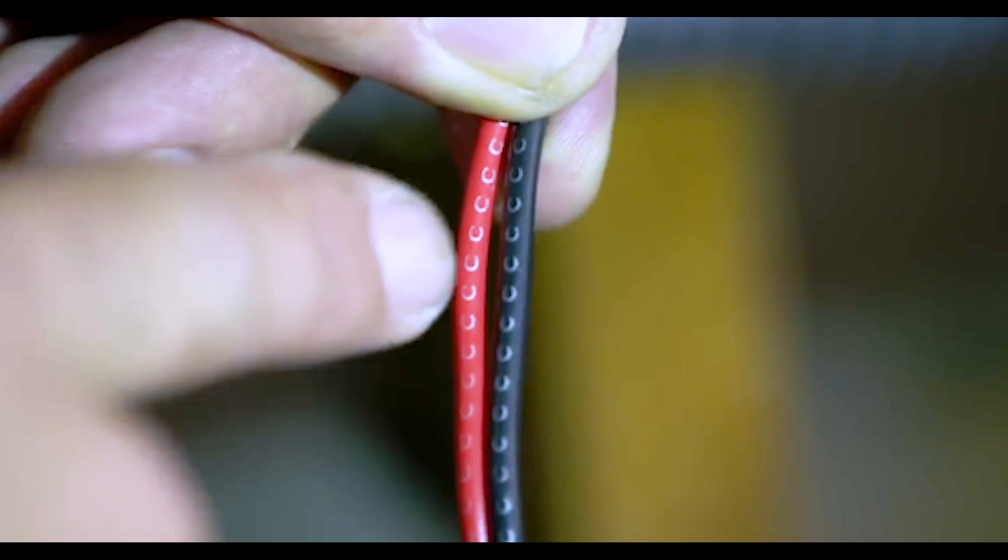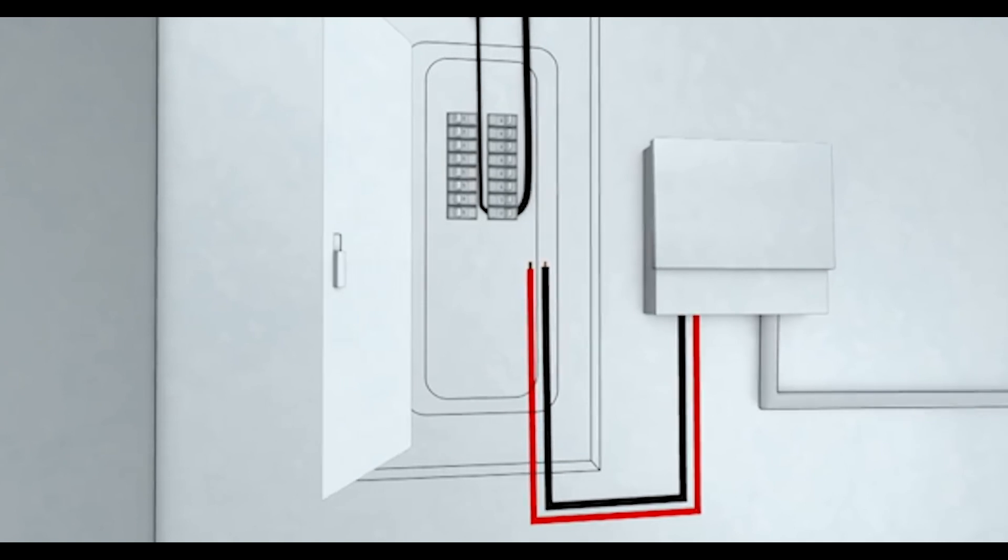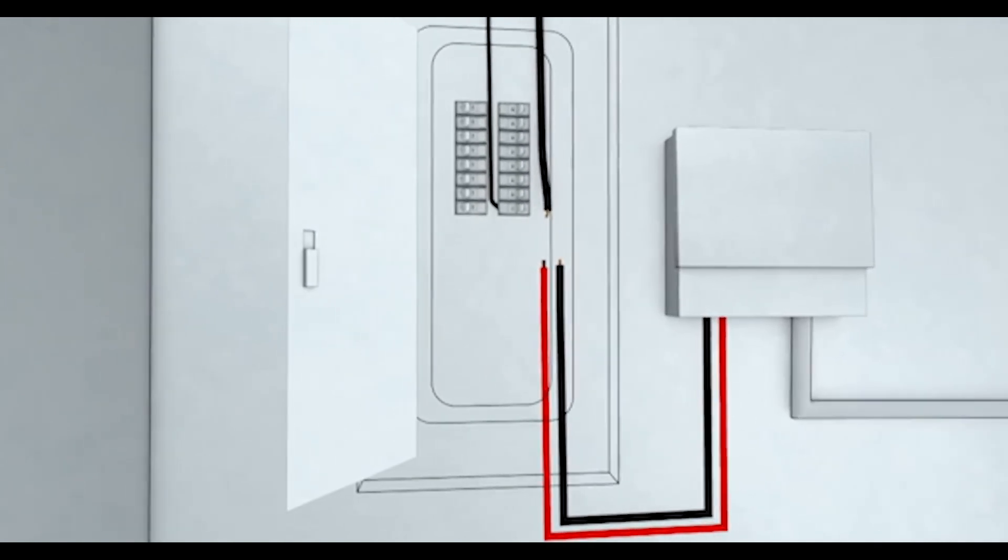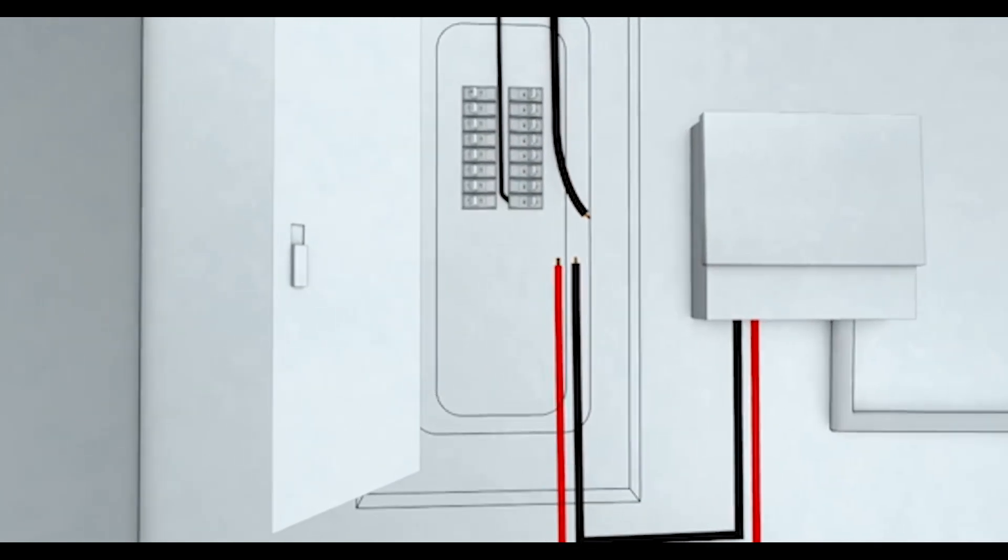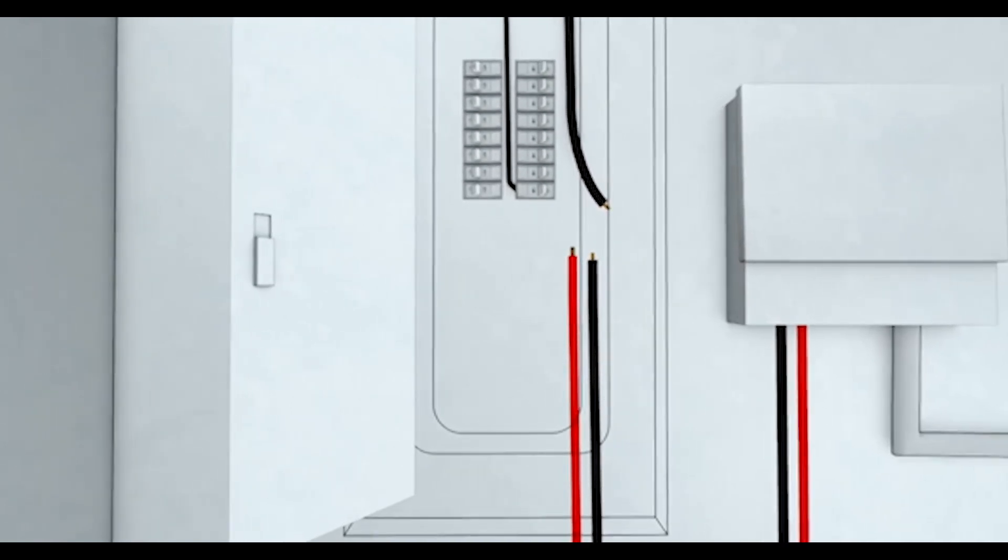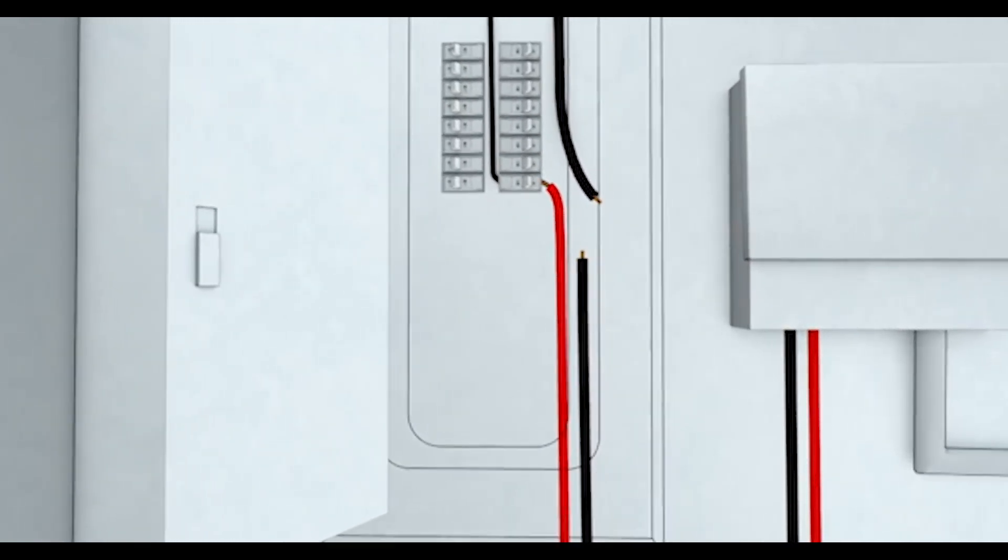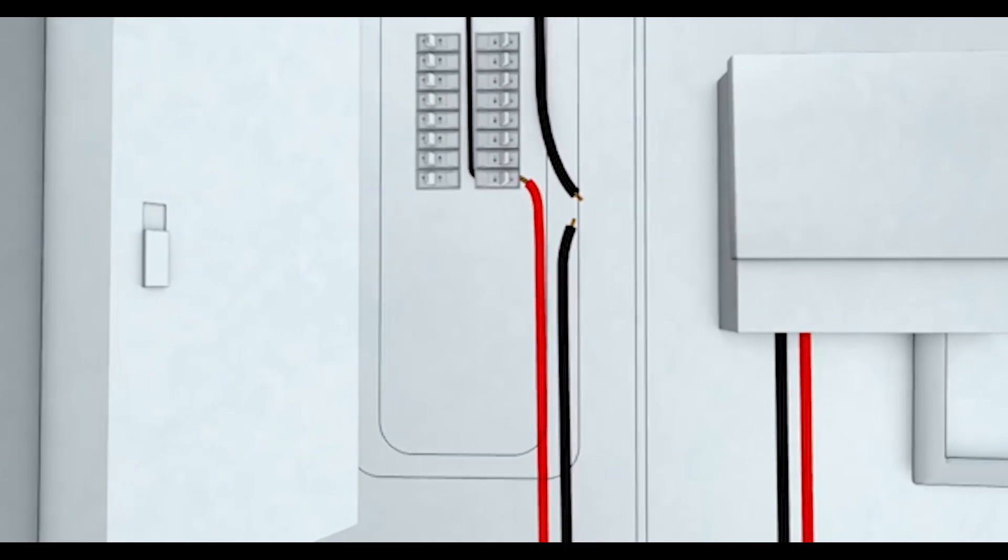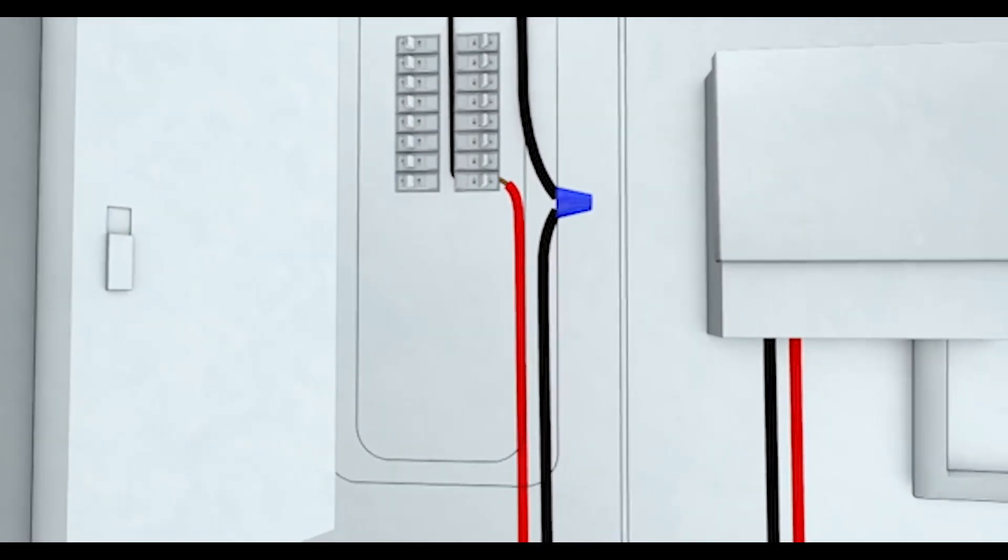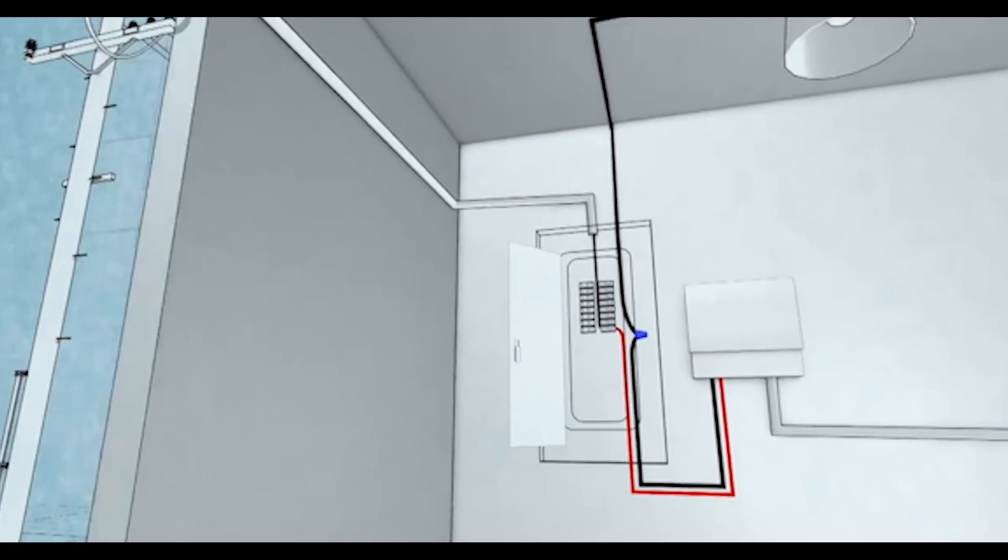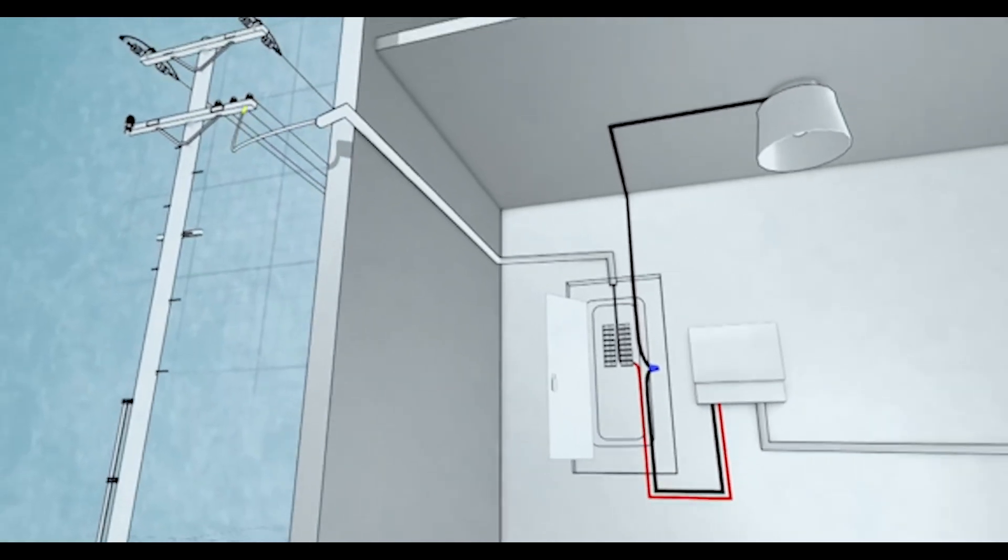And you want to identify the pairs on the red and black wires. Each wire will have a little stamp on it and so you want to identify the red and black A pair, the red and black B pair, C pair and D pair. Then you're going to go to your breakers. You're going to identify which breaker is going to be backed up. You're going to remove the wire that is ran to the breaker. A red wire is then going to be terminated on the breaker. Black wire is going to be connected to the black wire from the transfer switch for the A pair.